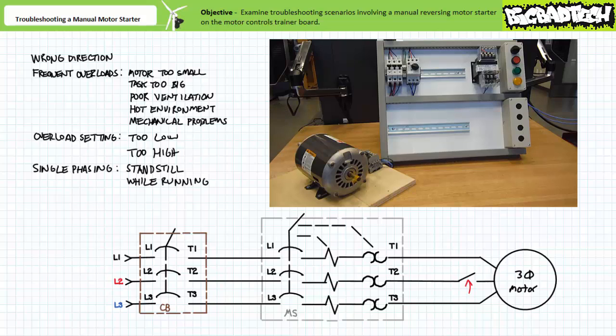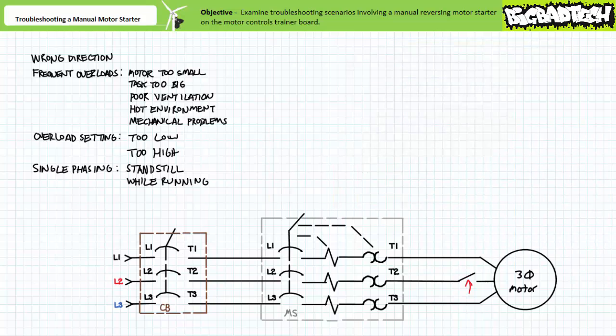If an operator allowed the overloads to cool and tried to restart the motor, the single phase motor at a standstill would not start and again enter an overload condition. Troubleshooting a single phased manual motor starter is the easiest of tasks. Given the sound and overload event clue you in onto the source, all you've got to do is determine which of the three phases is lost and then track down the open.